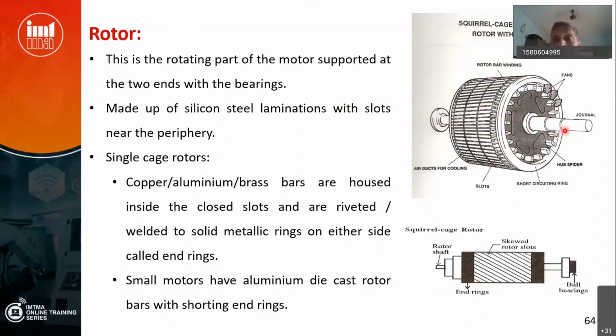So there is no connection. That is why we call it an induction motor: induction, self-induction, mutual induction. This is mutual induction, more or less the principle of a transformer. The primary is the stator winding, and the secondary is the rotor winding, shorted.